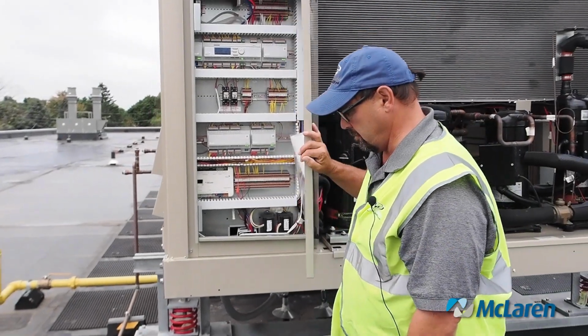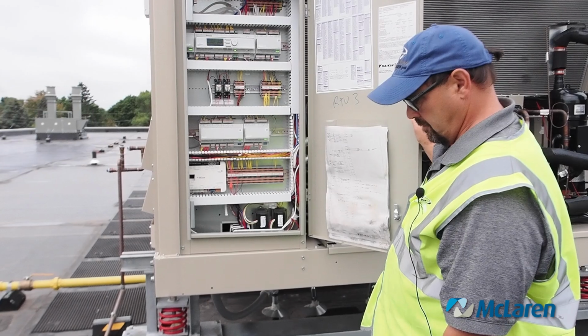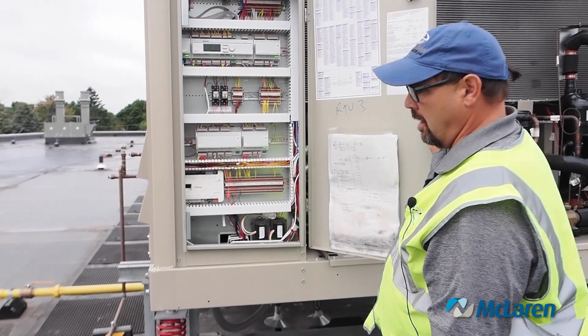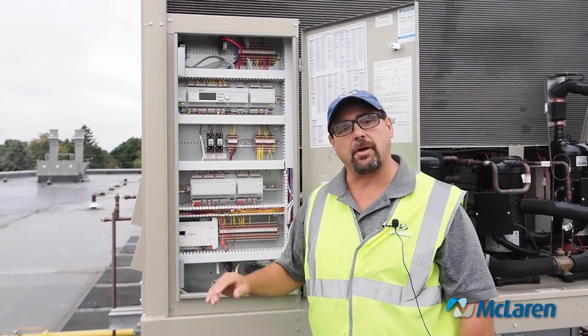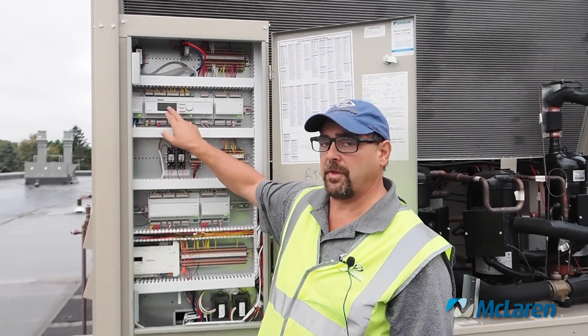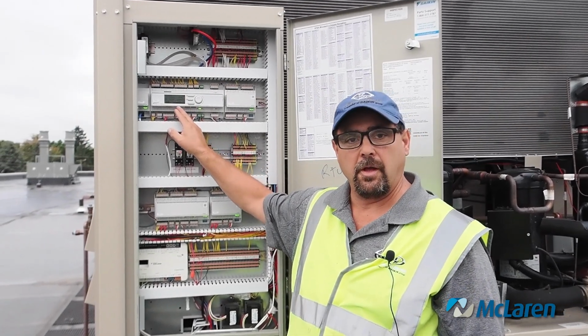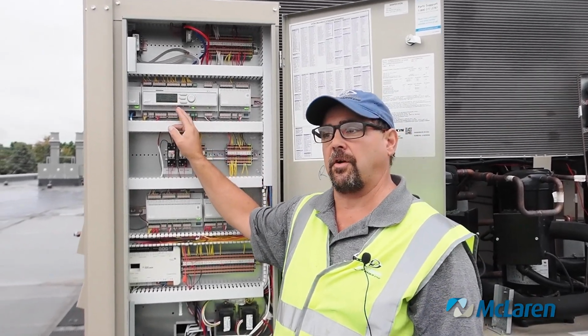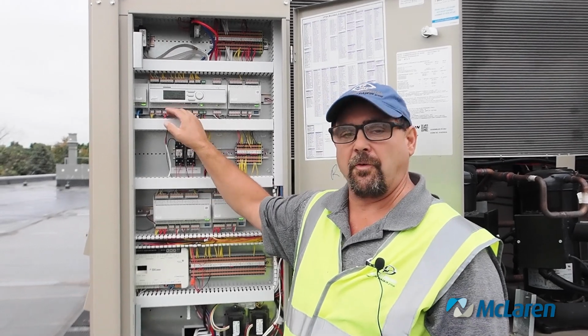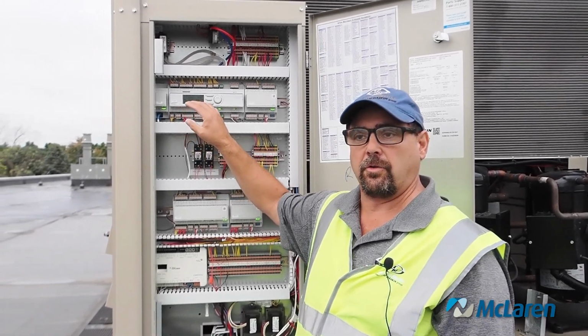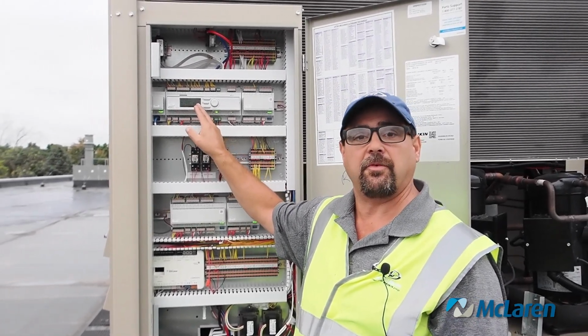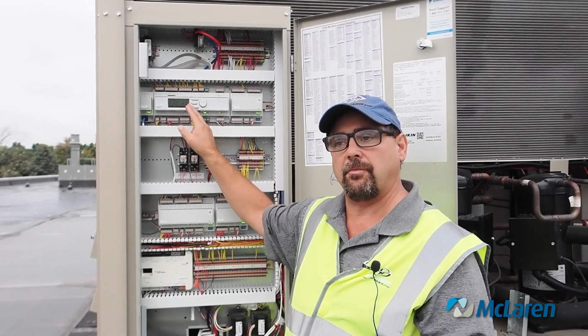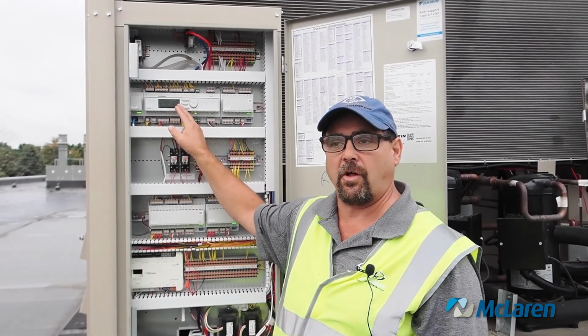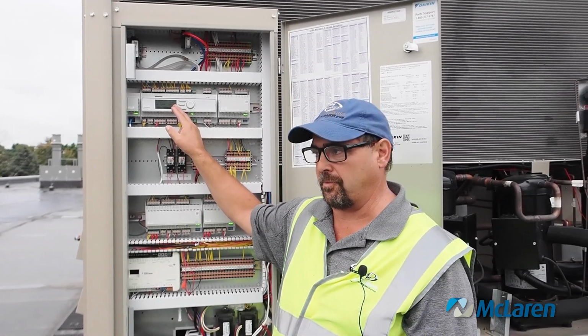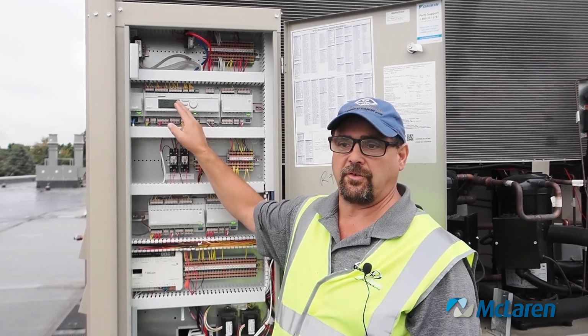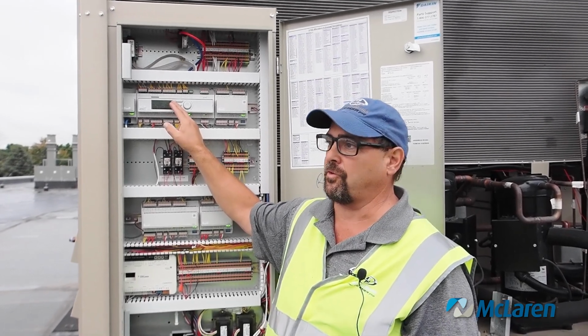So aside from the password part up there, is there anything else hands-on in that box? Not necessarily hands-on, but I would also reference this device when there's an alarm. If your building management system says there's a high pressure alarm, before you go down a rabbit trail, take this and make sure it says the same thing. Sometimes they get mixed up when they're writing these alarm points, and there's potential problems with that. So always reference this as the source of your problem first.